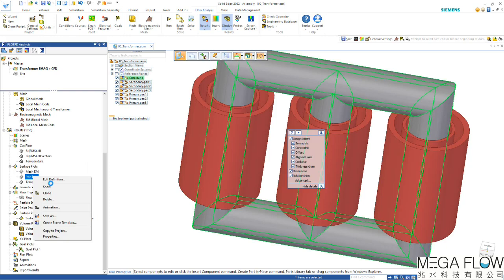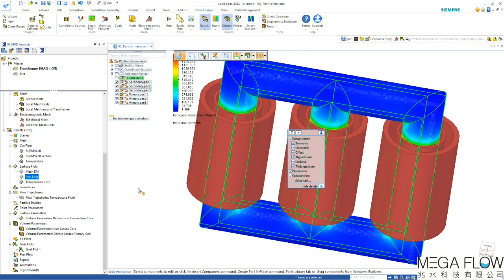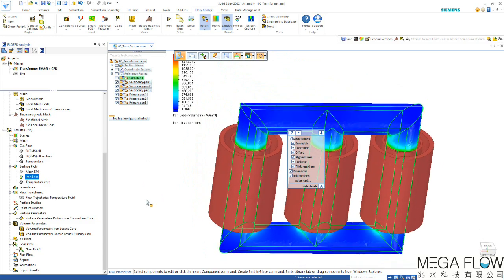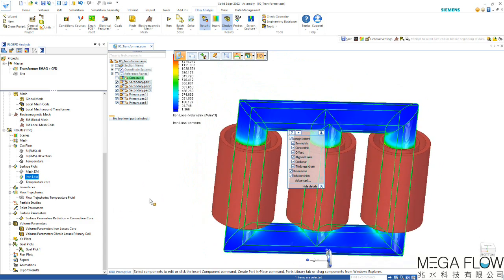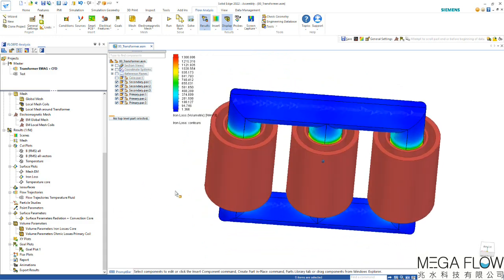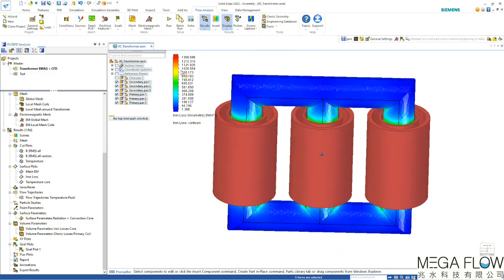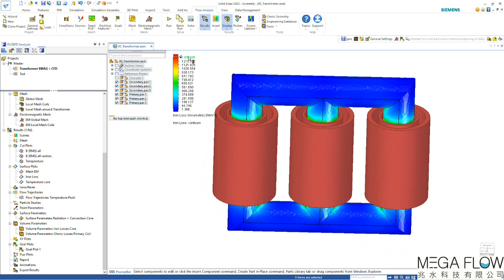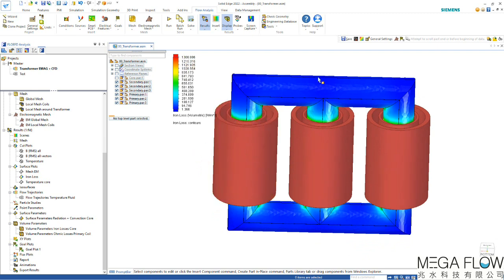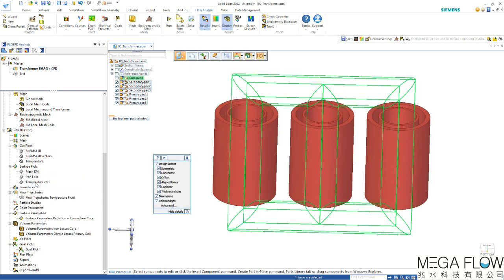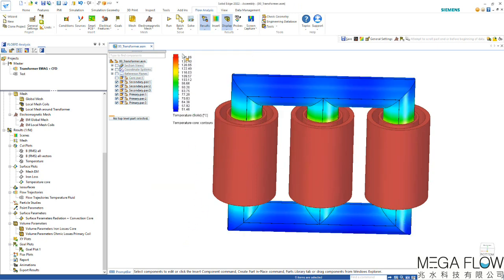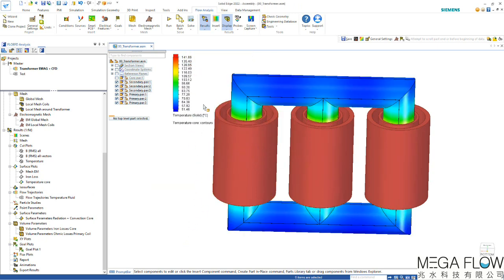We can also visualize the iron loss and if I hide the core you can see the visualization of these losses on the core. Hottest on the inside we reach around 1300 watts per cubic meter on the inside and much lower losses on the outside. Looking at the temperature on the core you can see it reaches 141 degrees on the inside and about 51 degrees at the colder positions here on the outside of the core.